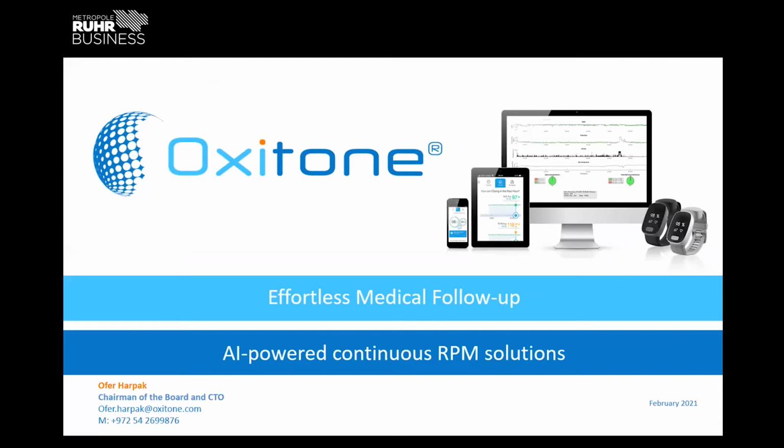platform. So we started with a device. The device is FDA and CE approved already. Actually, it's the first FDA approved pulse oximeter without any fingertip probe. Until now, we are the only one with a shipping product that is FDA approved and CE approved, of course, without any fingertip, which basically causes a limitation because you have to put it on the finger. It's measured once, and that's all. And basically all the parameters that we are taking are from the wrist.